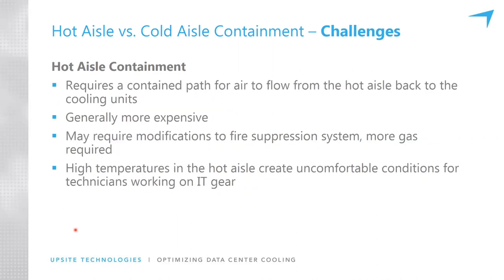Some of the challenges of hot aisle containment: it requires a contained path for the air to flow from the hot aisle back to the cooling units. And that most commonly takes the form of a drop ceiling used as a ceiling plenum return. Now, retrofitting an existing space with a drop ceiling to have a flow path means that you might have a lot of dust. It might be a very dirty space up there and that needs to be cleaned, as well as effects to the fire suppression system. It might require more gas if you are now using that above space for the flow path.